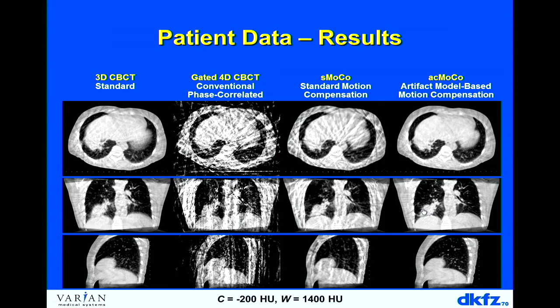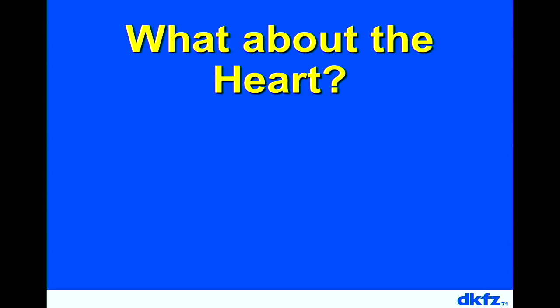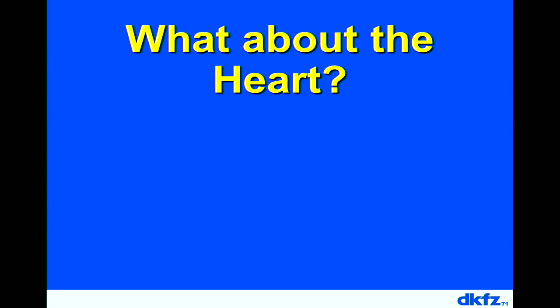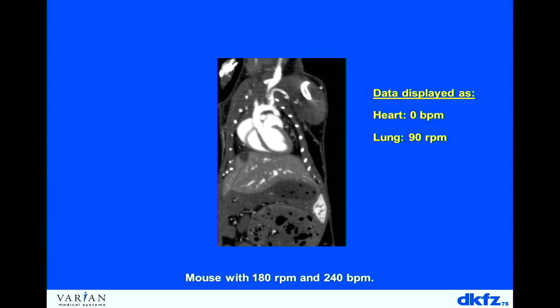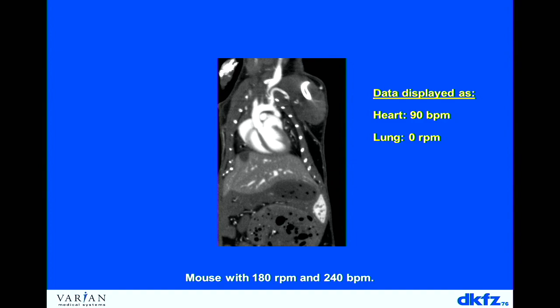Comparing results: gated reconstruction with artifacts, then standard motion compensation, then the cyclic artifact motion compensation — almost all artifacts are gone. Lung vessels and tumors are now clearly visible. This demonstrates the benefit of adding CT know-how to the registration approach. We also applied this to a mouse scan — with a heart rate of 240 beats per minute and 180 respirations per minute — to develop the method toward patient imaging. The mouse dataset is essentially five-dimensional: volumetric data for any cardiac phase and any respiratory phase.